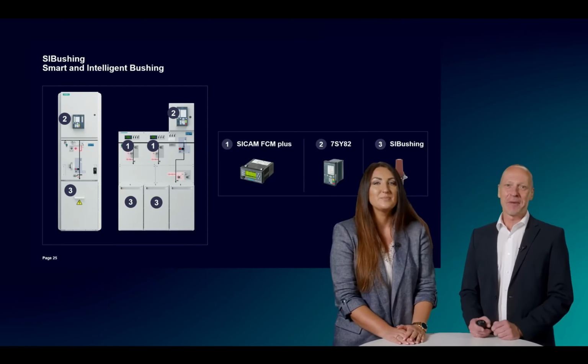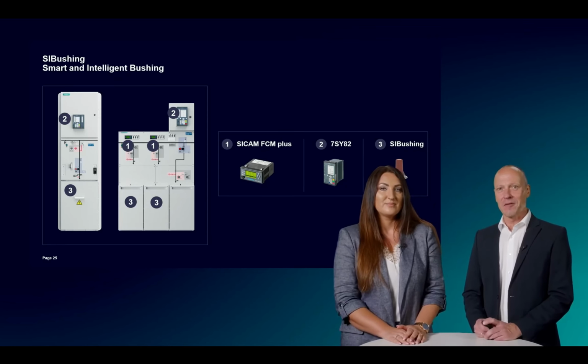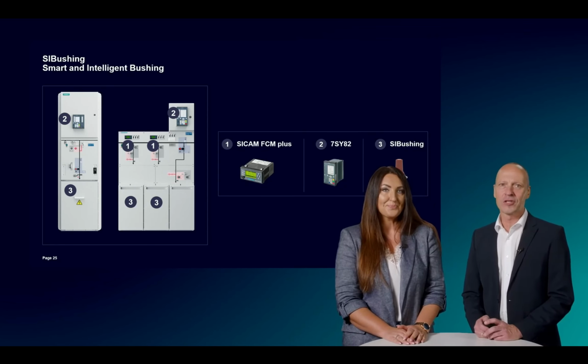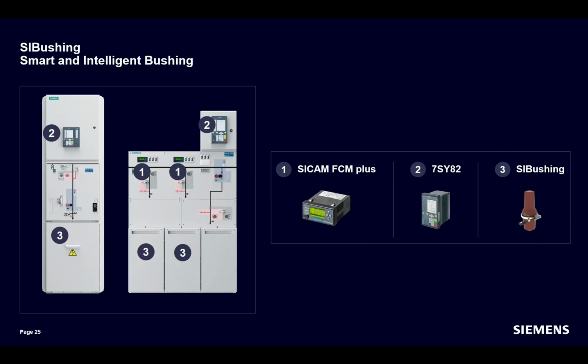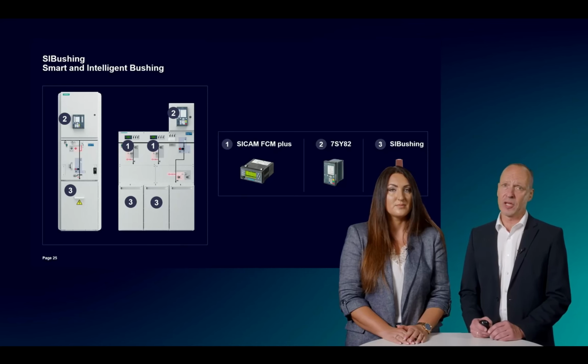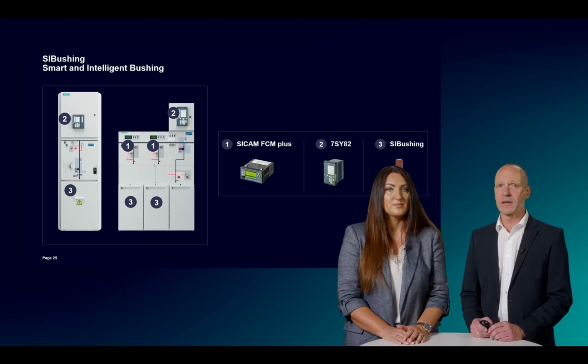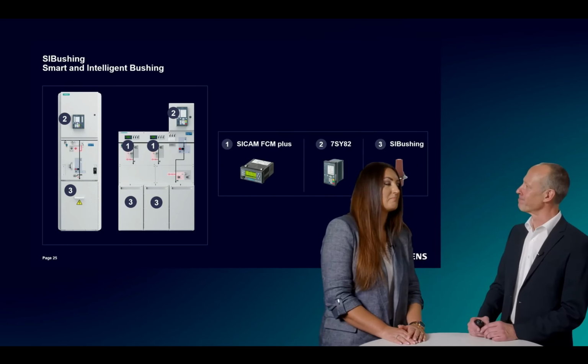But finally, I'm happy that we have now this innovative bushing available for all our GIS switchgear with outer cone Type C bushings. Together with the 7SY82, which is a universal protection relay with LPIT inputs, or the so-called SICAM FCM plus as a short circuit and directional indicator, we have a powerful system application in our portfolio. It provides functionalities for protection, indication, as well as load management, network fault management, and distribution grid management.